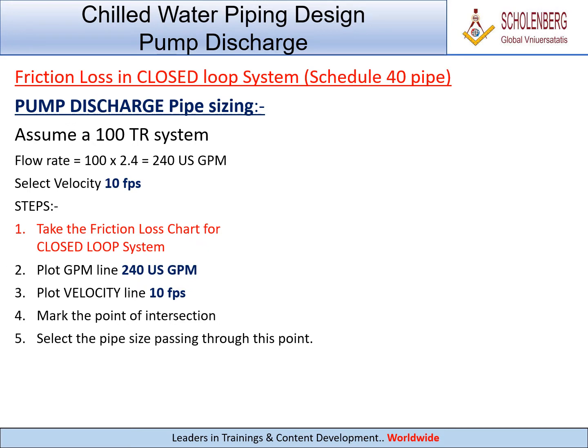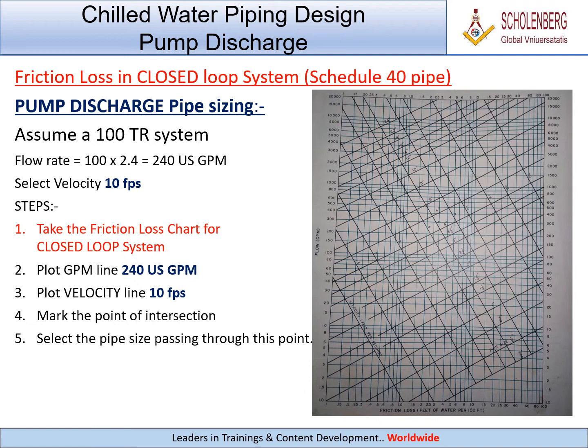Steps: 1. Take the friction loss chart for closed loop system. 2. Plot GPM line — 240 US GPM. 3. Plot velocity line — 10 FPS.